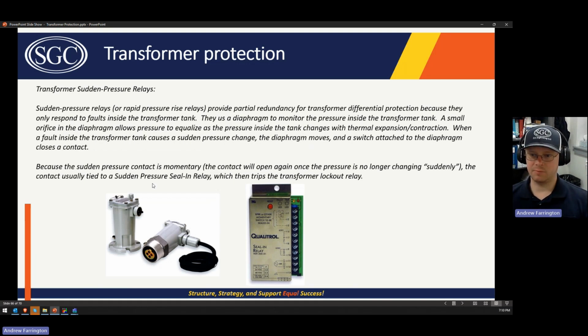Then there are other ancillary types of transformer protection. I think Adam has covered this already as far as sudden pressure relays. So if there's a fault inside the transformer, you can imagine that there's going to be arcing, rapid heating of the oil, and a rapid pressure buildup in the transformer due to that arcing. And so the sudden pressure or rapid pressure relay has a diaphragm in it that will detect that rapid pressure increase and expand. Because it's really meant to operate on that rapid pressure increase, eventually that's going to subside relatively quickly. And while the pressure may be higher than normal, it's not actively increasing.